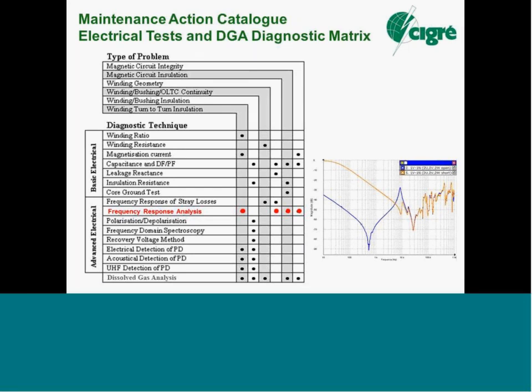So I've highlighted in red, just as an example, frequency response analysis. With those four red dots, FRA is good for detecting winding turn-to-turn issues because of the disturbance in the winding structure, the winding geometry, for changes in the physical geometry, whether it's collapsed, whether it's buckled, distorted. FRA is very sensitive. You'll see a change in the signature, especially between 1 kilohertz and 1 megahertz. You'll see changes in that band of frequencies if there is winding to winding geometry change.